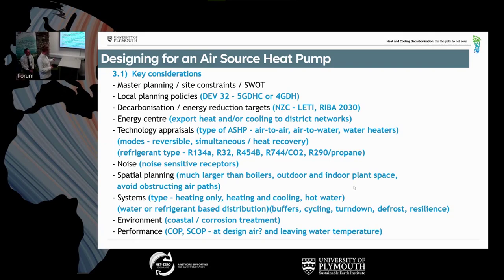And then the other one is performance. So it's a little bit hard sometimes to compare different heat pump performances. And a lot of manufacturers will quote air source heat pump figures at an air temperature of 7 and a leaving water of 35. Leaving water of 35 on a water-based heating system is exceptionally low, so it's not always realistic.